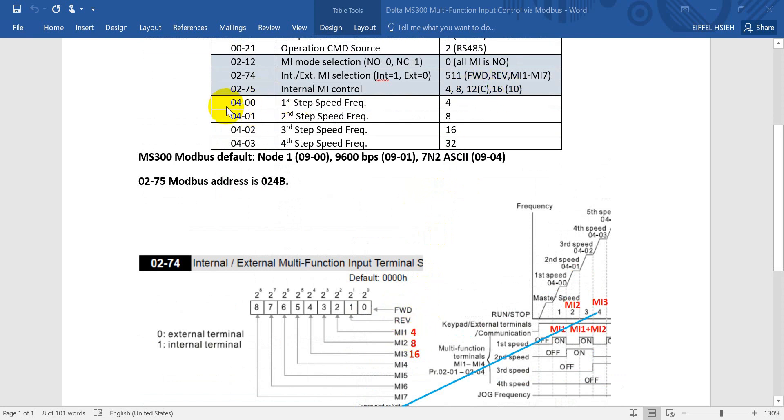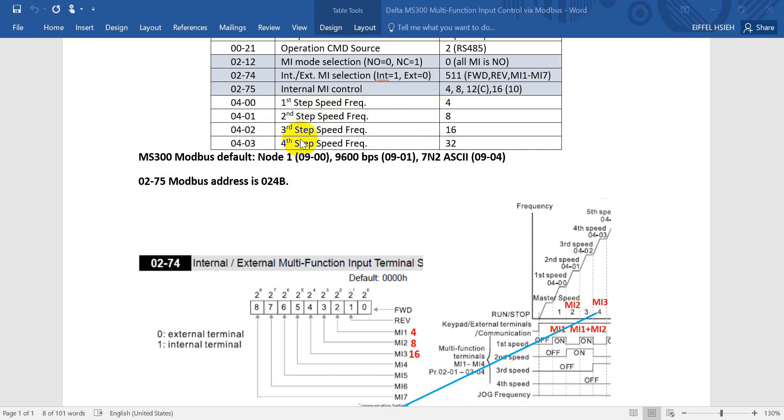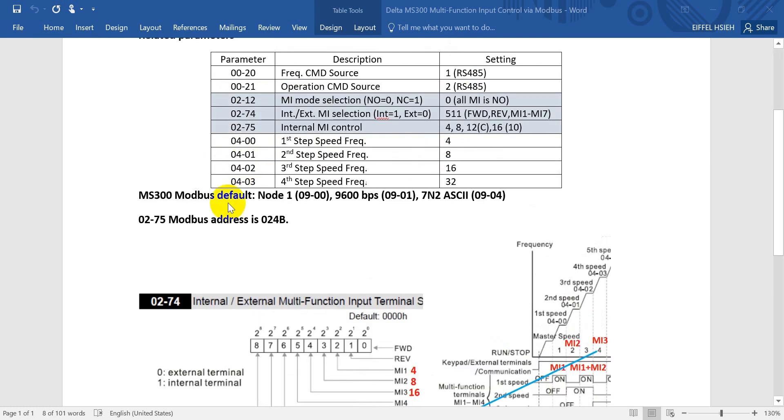You can consider P02-74 as the definition, and then P02-75 is to enable the function. Today's example will just show you MI1, MI2, and MI3. And then we also mix next. The parameters related with the multi-step speed - for the first step speed will be P04-01, second step speed will be P04-02, third step speed P04-03, and the last one is P04-04.